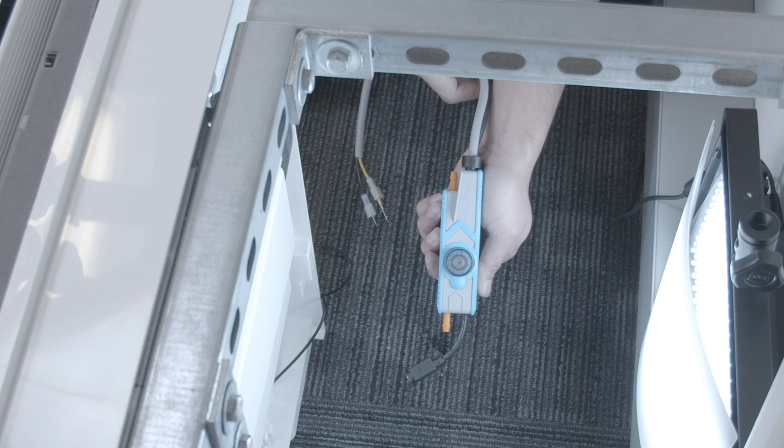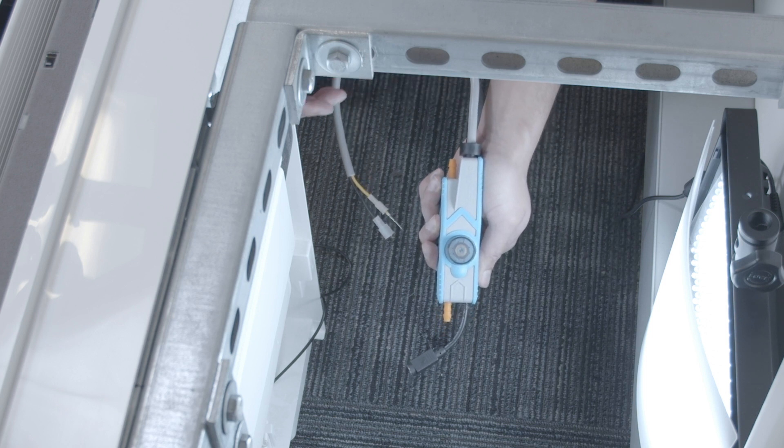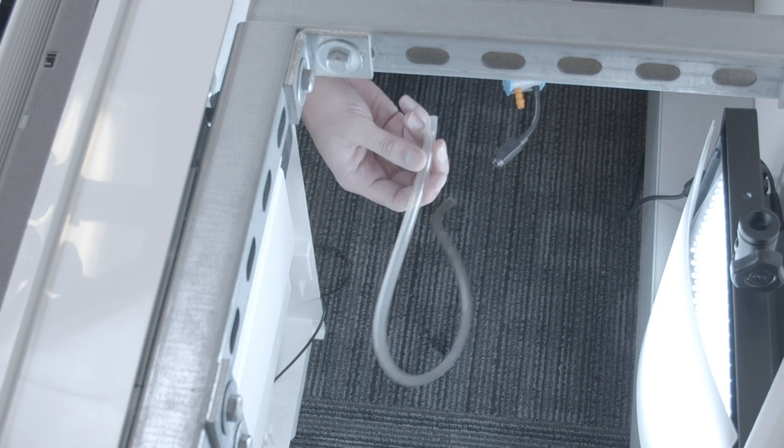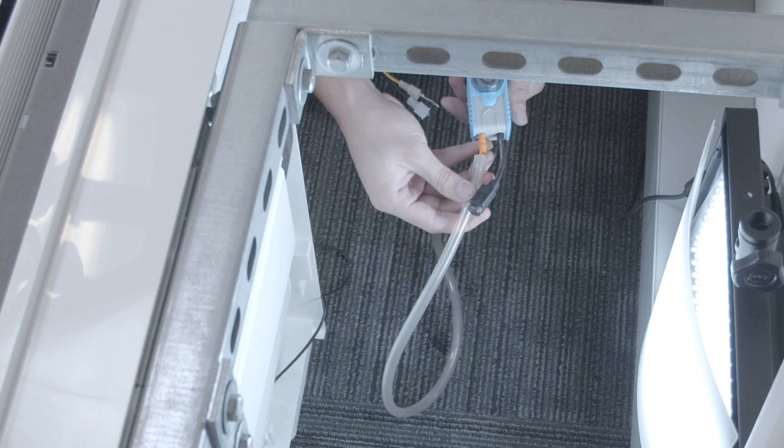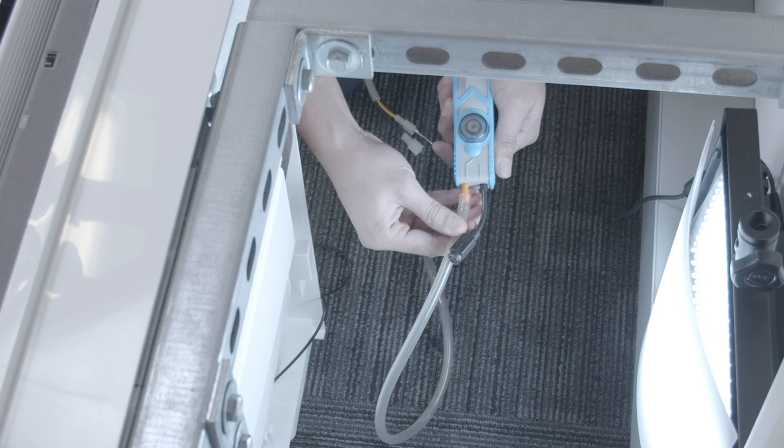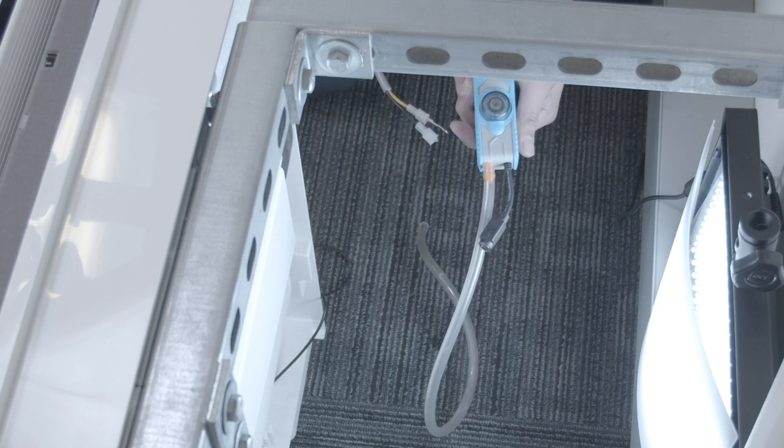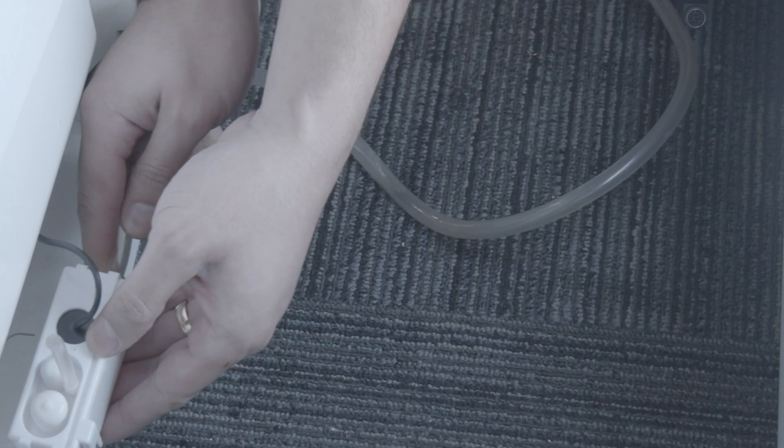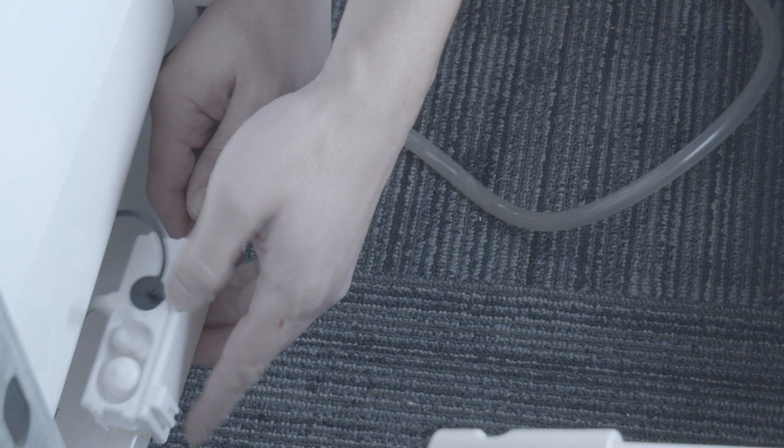Next, let's review the connections between the reservoir and the pump. Connect the field supplied condensate tubing to the inlet port of the condensate pump. Run the condensate tubing to the reservoir and connect to the outlet port of the reservoir.